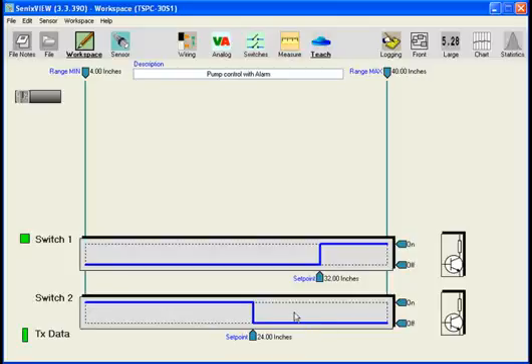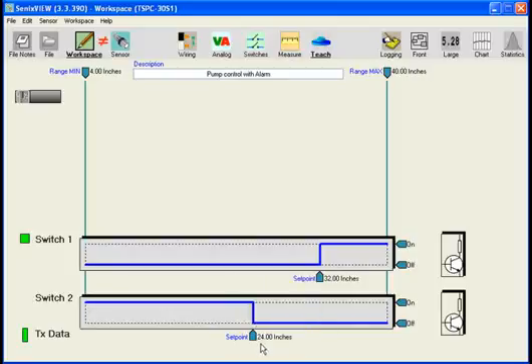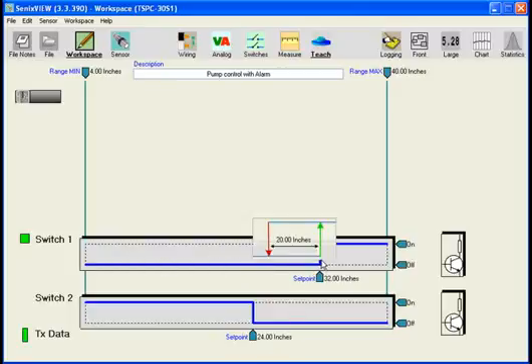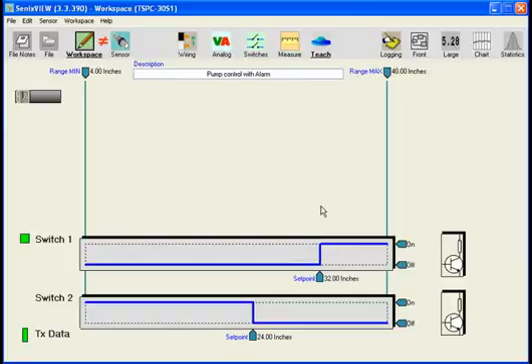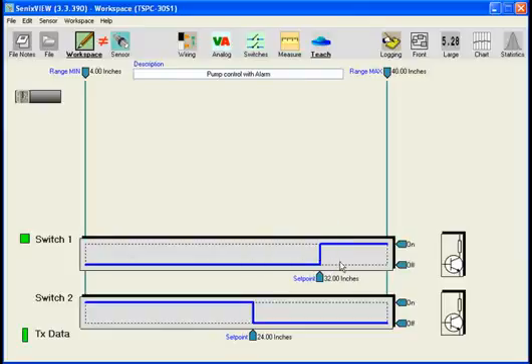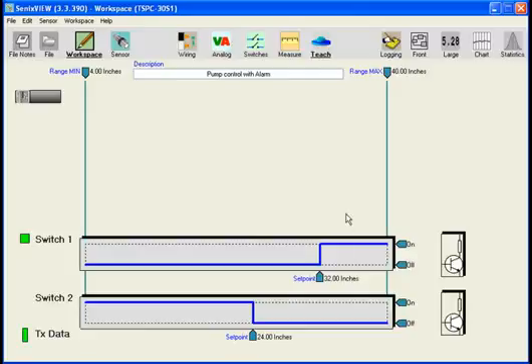Now comes the question. Where do we want the set point to be? Suppose your pump, when the level drops, takes a little while to build up. You might set a level, a warning, a low level warning. That could be a fail safe to keep you from driving the pump dry if there were no input fluid, for example.